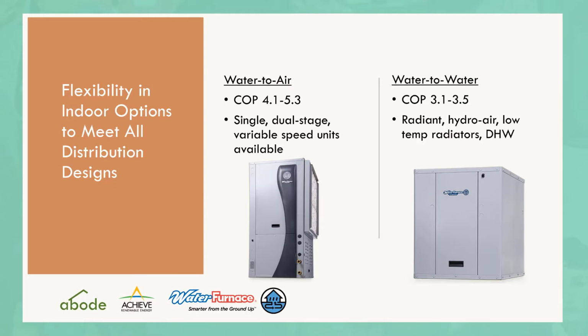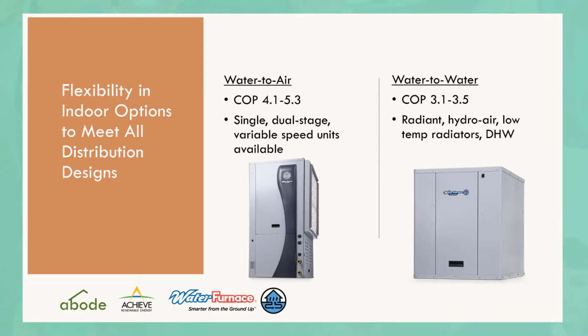In life, form usually follows function, so the equipment that replaces a residential furnace looks kind of like a residential furnace. And the equipment that replaces a boiler looks kind of like a boiler. This is a WaterFurnace variable speed heat pump, and this is what they like to call a packaged unit, meaning all the ground source heat pump stuff is down in this bottom compartment, and the air handler is in this upper compartment. So they are packaged together, and hence they call it a package unit. They are available in a split configuration where you'd have the geothermal units in a mechanical space and then refrigeration lines connecting to a remote air handler. The boiler replacement units simply heat or chill water to meet a hydronic demand.